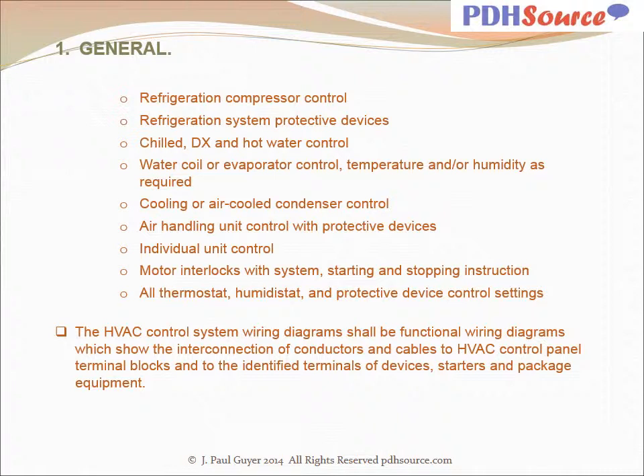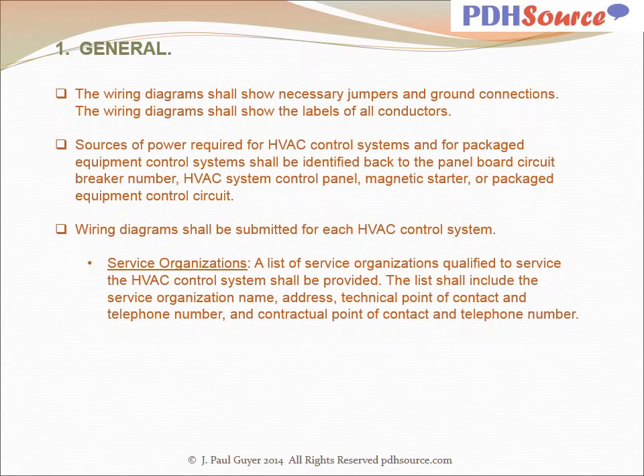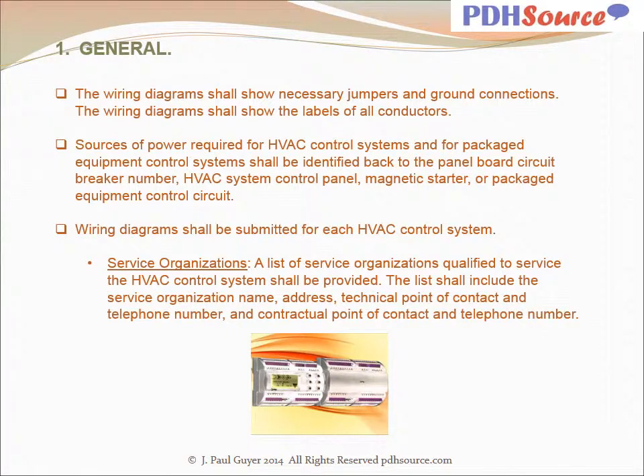The HVAC control system wiring diagrams shall be functional wiring diagrams which show the interconnection of conductors and cables to HVAC control panel terminal blocks and to the identified terminals of devices, starters, and package equipment. The wiring diagrams shall show necessary jumpers and ground connections. The wiring diagrams shall show the labels of all conductors. Sources of power required for HVAC control systems and for packaged equipment control systems shall be identified back to the panel board circuit breaker number, HVAC system control panel, magnetic starter, or packaged equipment control circuit. Wiring diagrams shall be submitted for each HVAC control system.